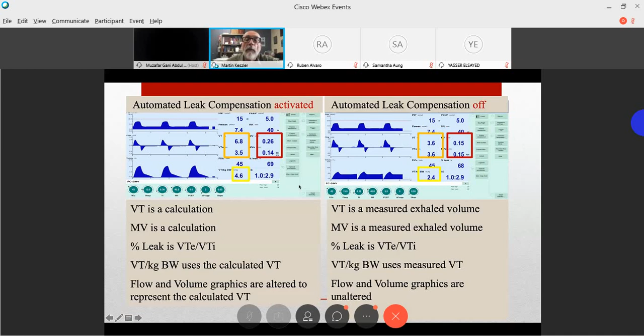But if you did not have the leak compensation activated, the machine would be using this uncorrected value. So it's drifted a little bit from 3.5 to 3.6, but pretty much the same, right? It would be using this value, 2.4 ml per kilo, and it would be cranking the inflation pressure up to try to bring this tidal volume up to your target. So this would be grossly overventilating the baby. So ventilating with a large endotracheal tube leak without leak compensation is one scenario where volume targeted ventilation can get you into trouble and cause overventilation. It is not a problem when you use the leak compensation. It's really cool. All right, we're going to talk about some practical aspects now.